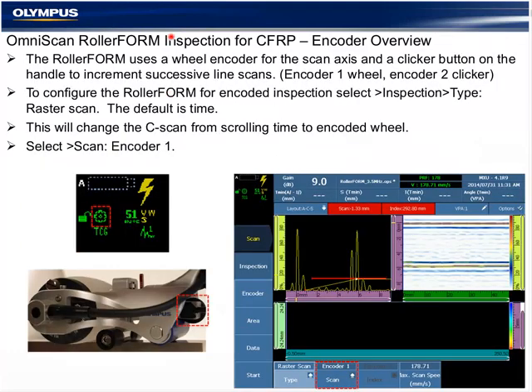So the first part of this is the encoder 1, and to put the instrument in encoder 1 scan, we're going to select Scan Menu, Inspection, and we will change our type from time, that we saw a little clock in the notification area, to raster. When we select raster scan, it will slave one of the encoders that we select to the scan menu. So when we select encoder 1 here, which is wired to the wheel on the rear wheel guide, it will slave this wheel encoder to the blue axis, also called the scan axis.